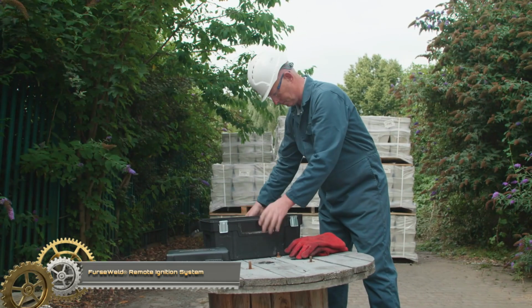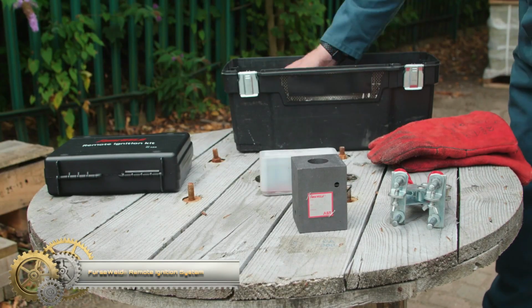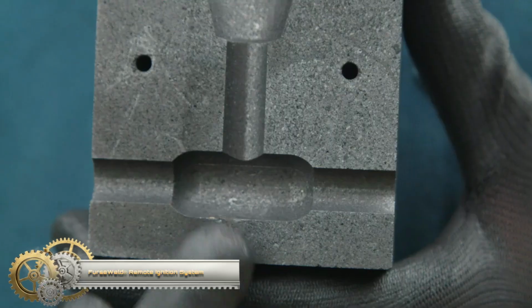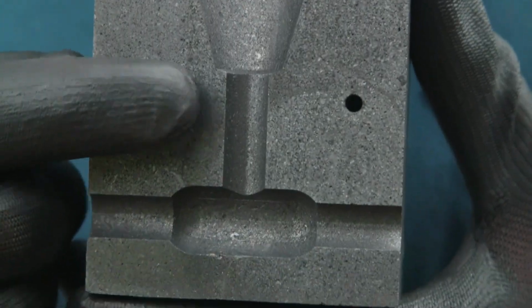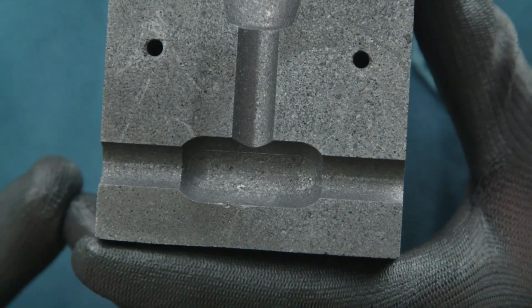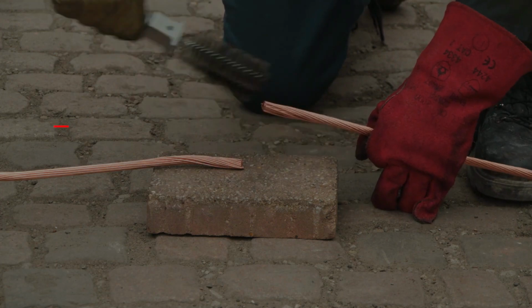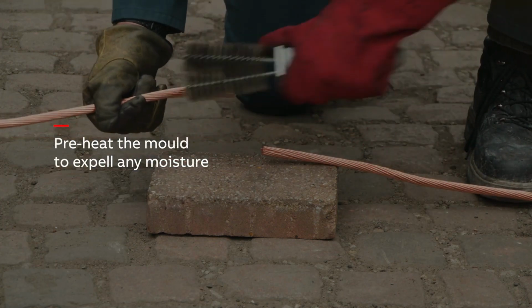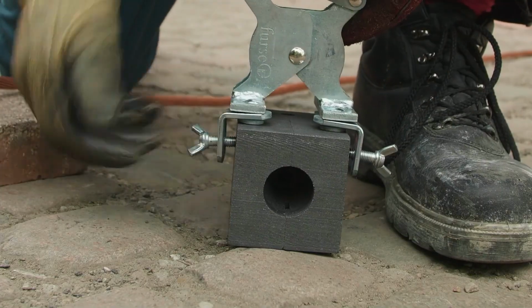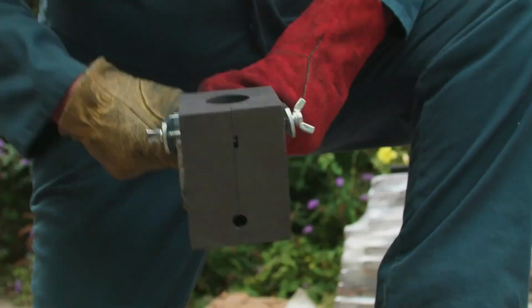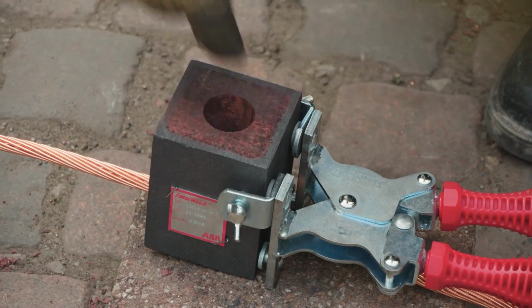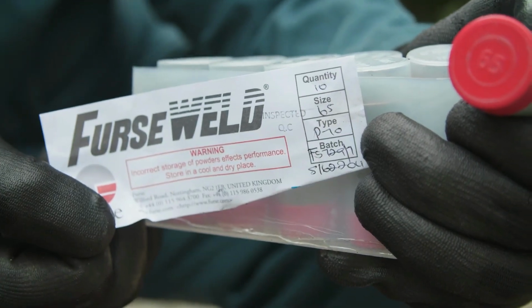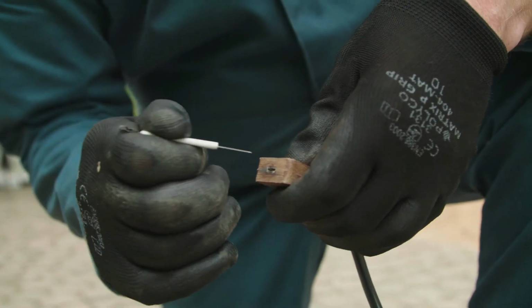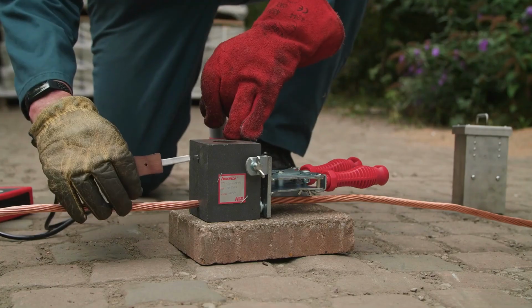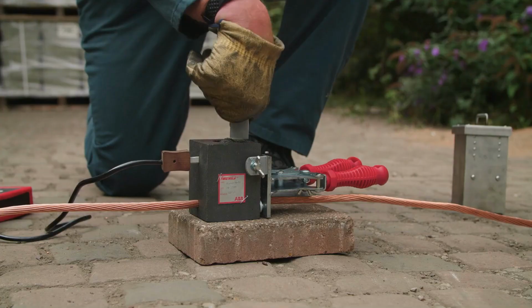The FurseWeld remote ignition system for exothermic welding is a simple, portable, and cost-effective method of welding copper to copper or copper to steel through the high-temperature reaction of powdered copper oxide and aluminum. Using the FurseWeld remote ignition system removes the need to use ignition starter powder with a traditional flint gun, allowing ignition from a safe distance whilst also reducing exposure to smoke and fumes.